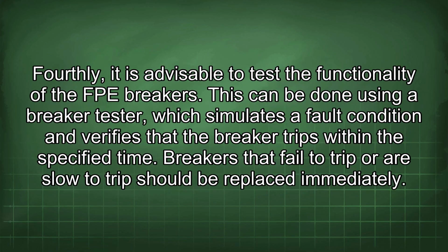Fourthly, it is advisable to test the functionality of the FPE breakers. This can be done using a breaker tester, which simulates a fault condition and verifies that the breaker trips within the specified time. Breakers that fail to trip or are slow to trip should be replaced immediately.